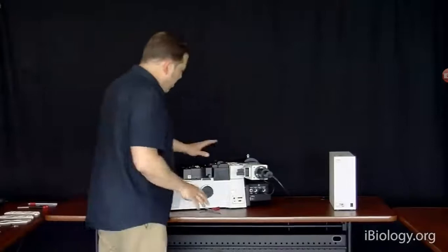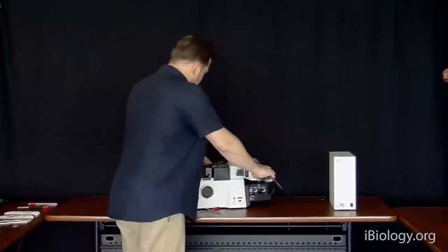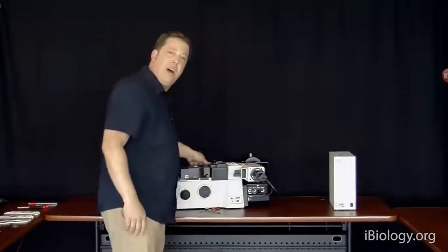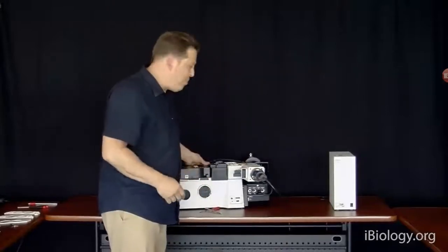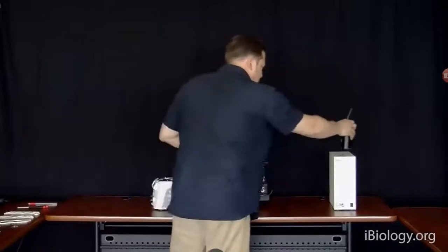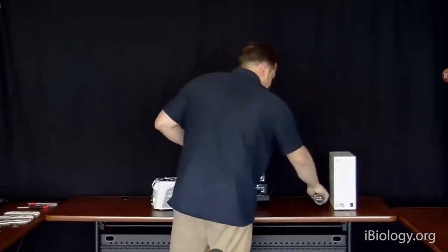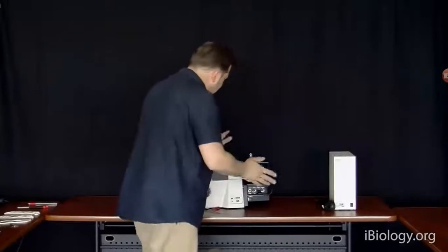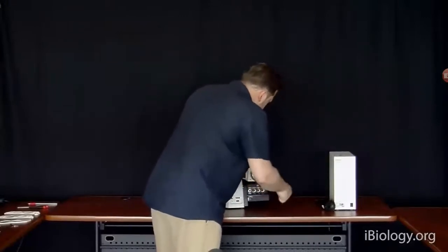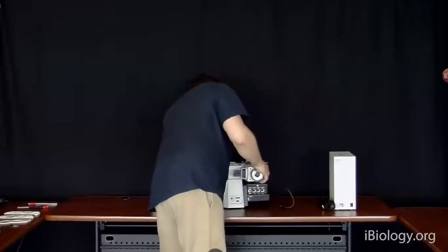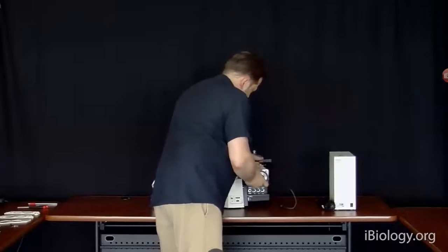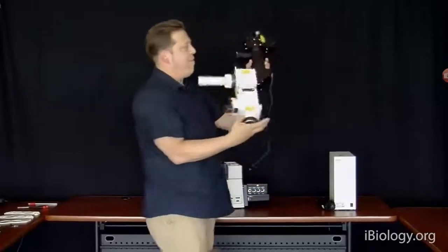Okay, so now we're really getting down to the base of this microscope. Since I've loosened it all up, let me pull off and go through the fluorescence or epi illumination on the microscope. First, disconnect our light source. We'll go through that in a little more detail. And here is the epi illuminator, which in this case has two motors. Pull that off of the microscope.